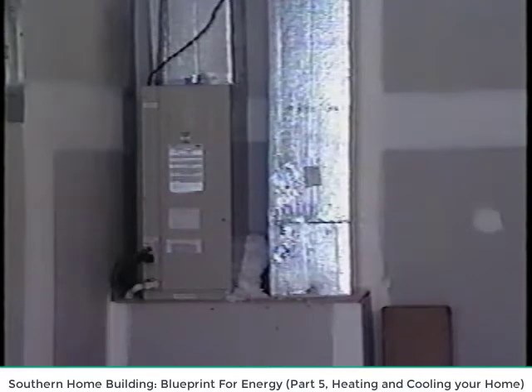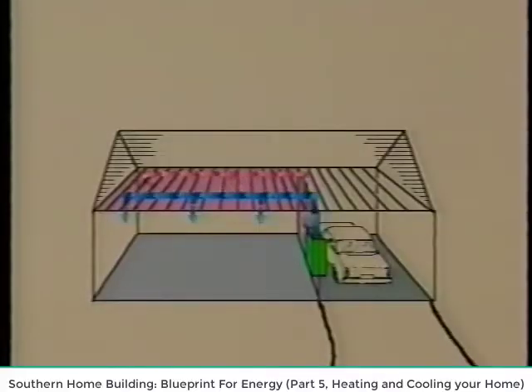Another opportunity for savings is through the design of the distribution or duct system. This is a typical distribution system. In the summer, air cooled in the air handler, shown in green, is supplied to the rooms through a supply duct, shown in blue. The cooled air passes through the rooms of the house and picks up the heat. All of this air is then returned to the air handler through the return duct, shown in red.